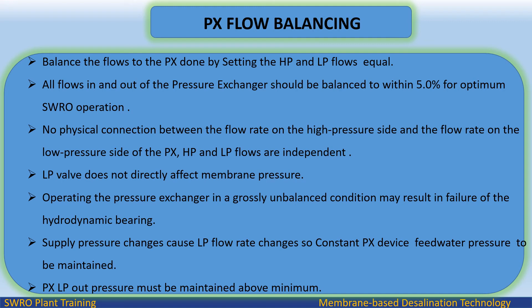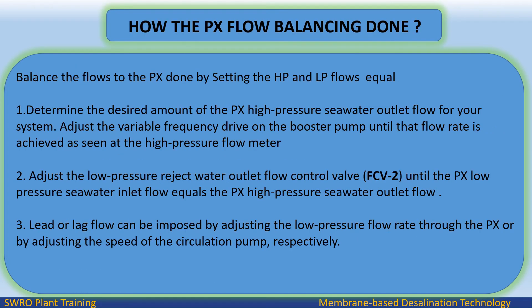PX flow balancing: balance the flows by setting HP and LP flows equal. Step 1: determine the desired PX high-pressure seawater outlet flow, then adjust the variable frequency drive on the booster pump until that flow rate is achieved at the high-pressure flow meter. Step 2: adjust the low-pressure reject water outlet flow control valve until the PX low-pressure seawater inlet flow equals the PX high-pressure seawater outlet flow. Lead or lag flow can be imposed by adjusting the low-pressure flow rate through the PX or by adjusting the speed of the circulation pump, respectively.